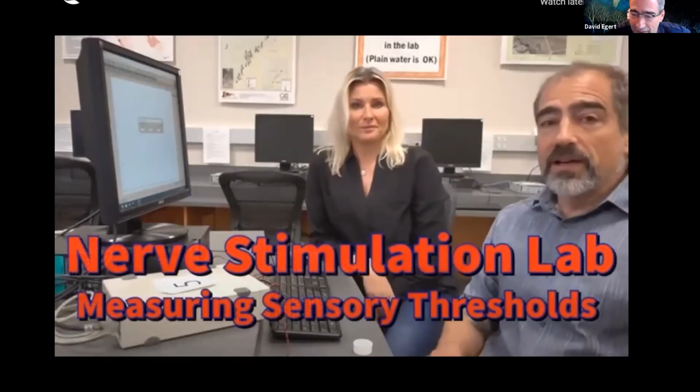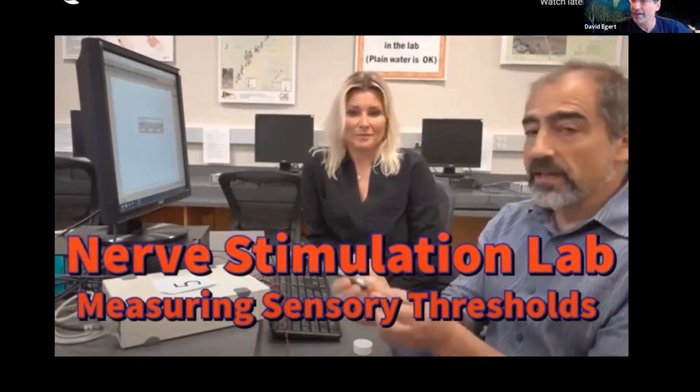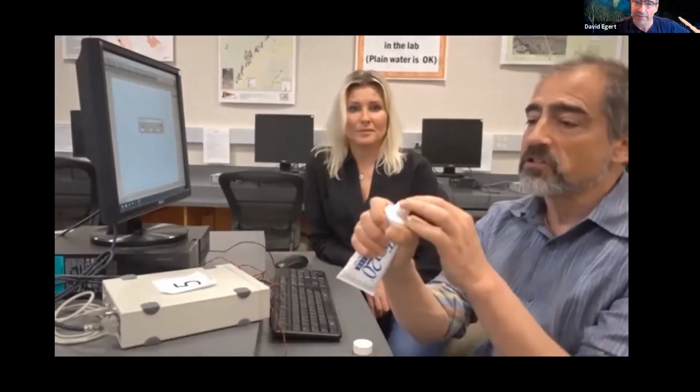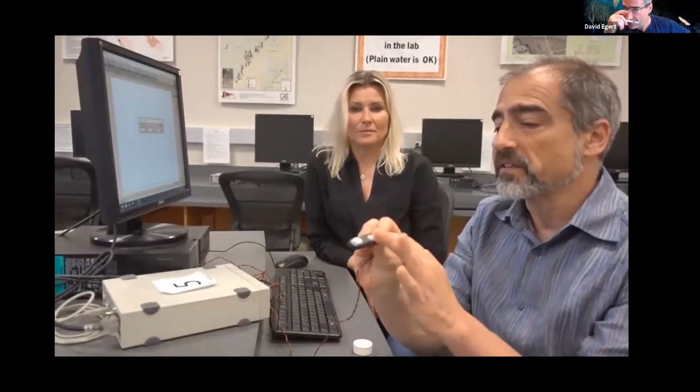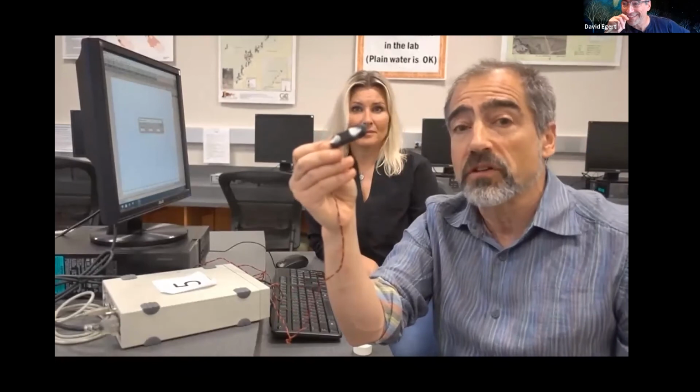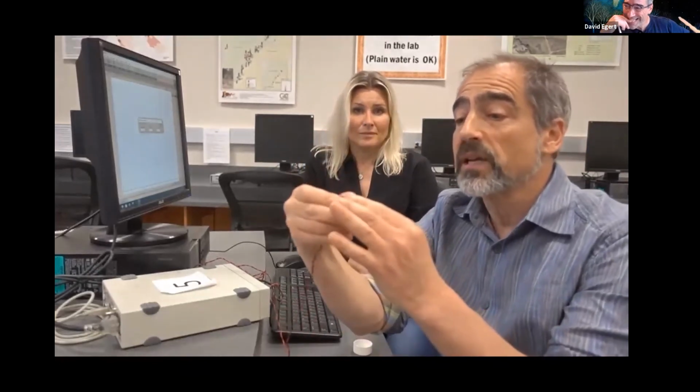All right, so I'm gonna be the subject. Here are the electrodes. This is the little bar electrode. I'm gonna get our little conductive gel to make sure there's a good connection between the electrode and my skin, about half of a split pea. You don't want too much that's going to goop everything up, but you want to make sure there's enough so there's a very positive contact between the electrode and your finger, and also it holds it on well. When you do the calf, we actually have little Velcro straps to make sure that the electrode is also firmly pulled against your calf. But for your finger, that gel works great.